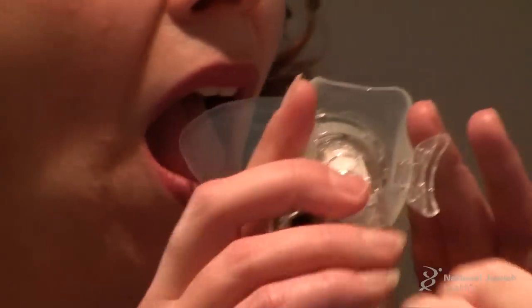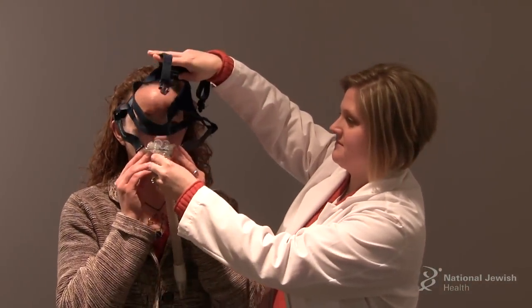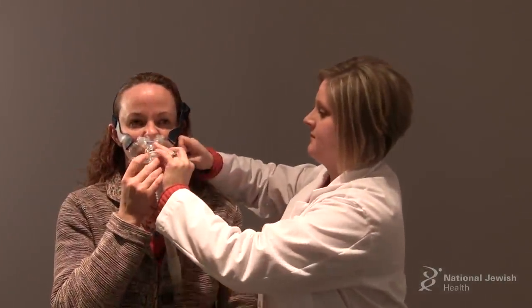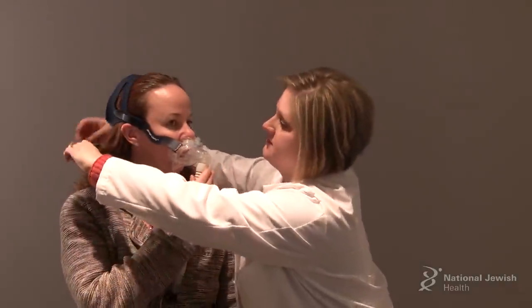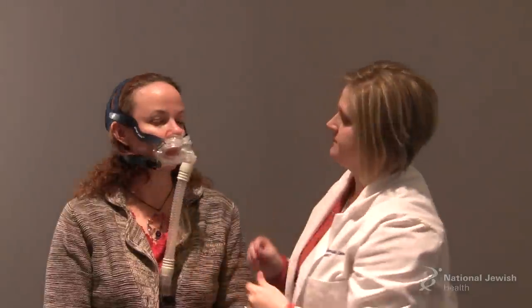There is one oral mask on the market — part of it goes in the mouth and part goes on the outside over the mouth. Because of the part that goes in the mouth, it can cause tooth pain or sores on the gums for some patients, so these aren't generally well tolerated and are rarely used. There is also a hybrid mask, which is a combination of nasal pillows and an oral mask that covers the outside of the mouth. This is very helpful for people who breathe through their mouth but have trouble with full face masks irritating the bridge of their nose.